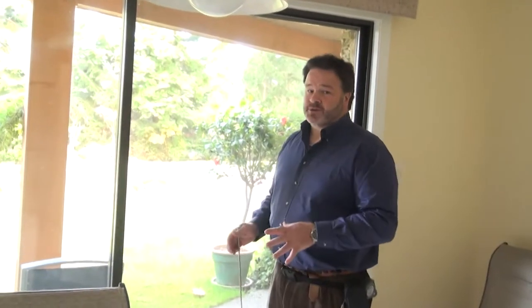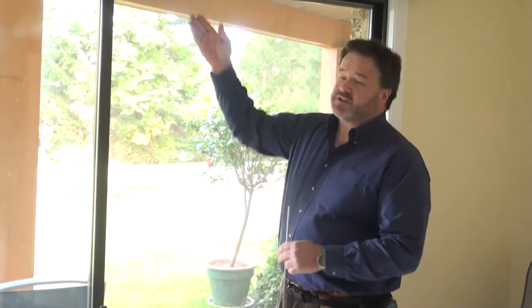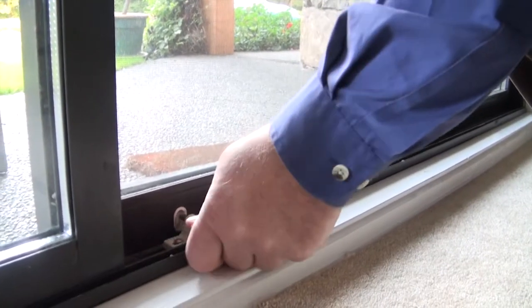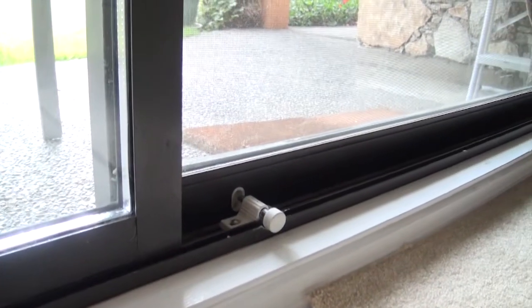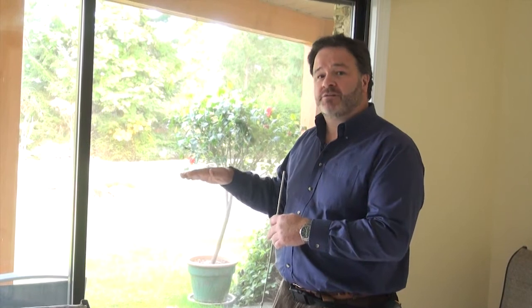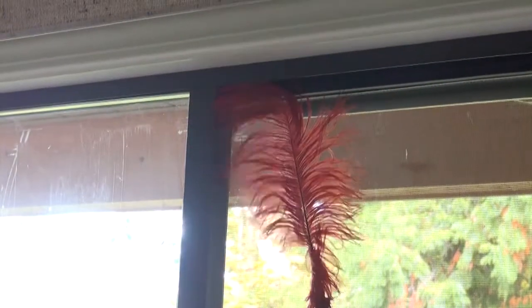Sliding doors are a pretty common source of air leakage in houses. They tend to leak mostly at the top and at the bottom. What happens is, as the door ages, the track at the bottom and the rollers in the bottom of the door wear out because there's a lot of weight on them as the door gets opened and closed. So the door gradually shifts down lower, which moves it out of alignment with its seals, and it starts leaking. So let's just check this one and see how it looks. Wow, that's a really significant leak. I would definitely be recommending to this homeowner or to a prospective buyer that they consider changing out this door for a new one.